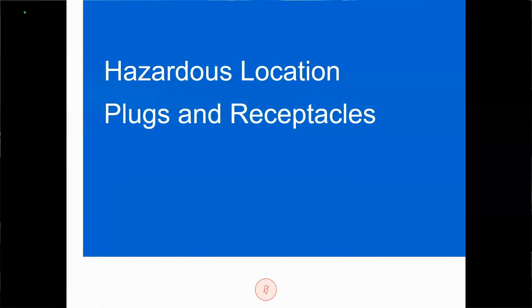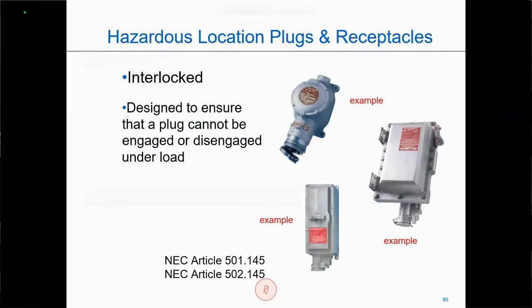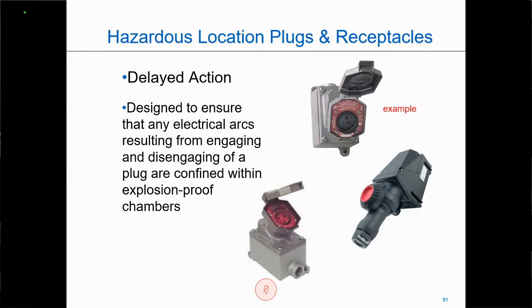When it comes to hazardous location plugs and receptacles, if you think about when we unplug the toaster or the iron in the morning, that spark that we get, or that little blue flash, would be bad in a hazardous location. So here we have interlocked units which don't allow us to engage or disengage under load. We also have dead front units, and this is an example of a convenient unit, that convenience outlet, that when I put the plug in, nothing happens. It only goes in part way. I flip a switch here, and then the plug goes in the rest of the way. When I want to disconnect, I pull the plug and it comes out part way, and then I rotate the switch back, and the plug will disengage. Everything has been contained inside the unit.